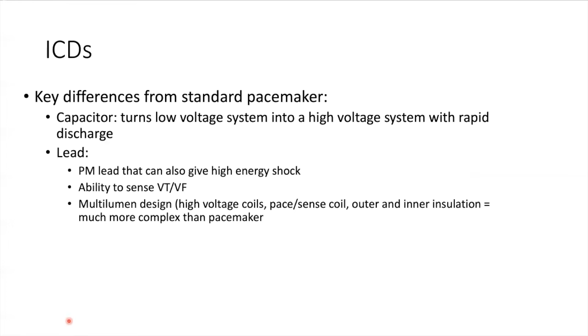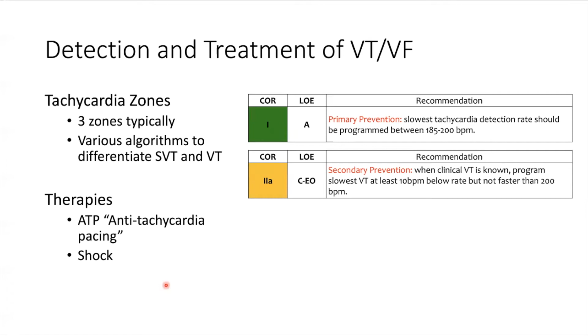The way we program ICDs is a little bit different than pacemakers. One, we always include pacemaker programming. So the patient will be set VVI 40 as a backup or DDD 60, but they also set up tachycardia therapy zones, monitor zones, and therapy. Generally, we have 3 zones to program, say maybe a slow VT zone at 150, a regular VT zone at 180, and then a fast VT zone at 200, for example. And during each of these zones, we'll program therapy. So maybe the lowest zone will have some ATP and then a shock. Second zone will have some ATP and then shocks as well. And the third zone might just have ATP while charging and then shock therapy.